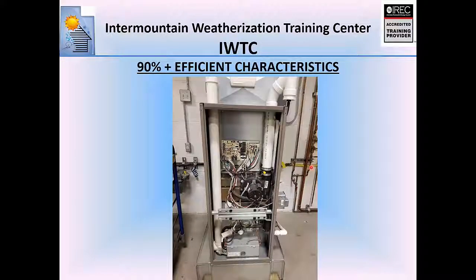Okay, now there are some exceptions to the burners up high rule. This particular furnace is what we call a downflow. That's another basic thing you need to know. Furnaces can blow air different ways. So the air in this furnace is sucked through the return, goes down through the furnace, and then is delivered into the house. Notice on the downflow, the burners are not on top anymore, they're down low. And the blower motor's back behind this door. So the blower's on top, that means the air is blowing down. But if I were to flip this furnace over, which I can because it's a multi-poise, the burners would be back up on top when it's in upflow condition.